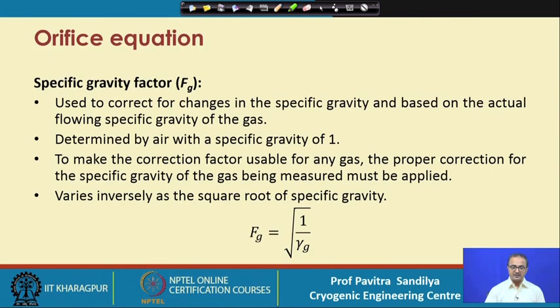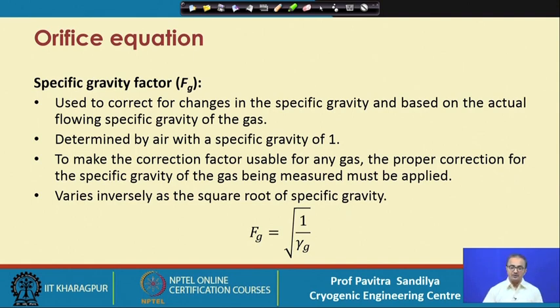The specific gravity factor corrects for changes in specific gravity, which can change due to changes in density as a function of temperature and pressure during flow. It is determined relative to air with a specific gravity of 1, and the correction is given as the square root of the inverse of the specific gravity.